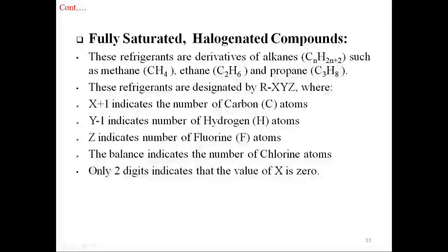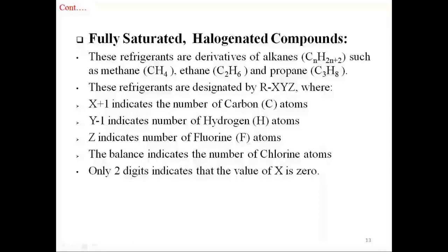Fully saturated compounds. These refrigerants are derivatives of alkanes (CₙH₂ₙ₊₂), such as methane (CH₄, N=1), ethane (C₂H₆), and propane (C₃H₈). These refrigerants are designated by Rxyz, where x+1 indicates the number of carbon atoms, y−1 indicates the number of hydrogen atoms, z indicates the number of fluorine atoms, and the balance indicates the number of chlorine atoms. Only two digits indicates that the value of x is 0.